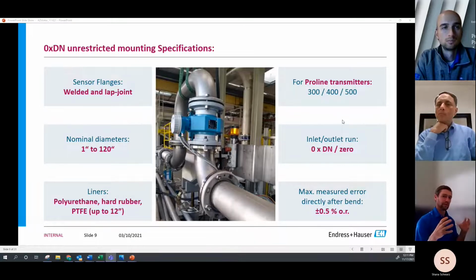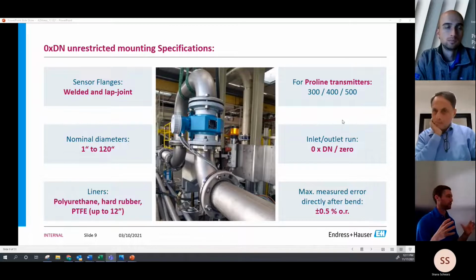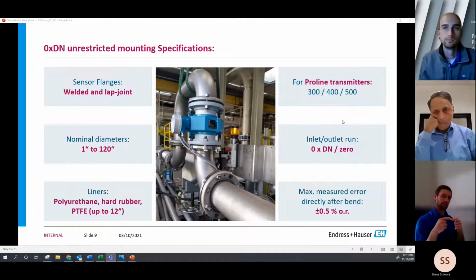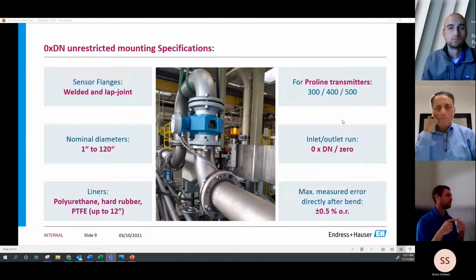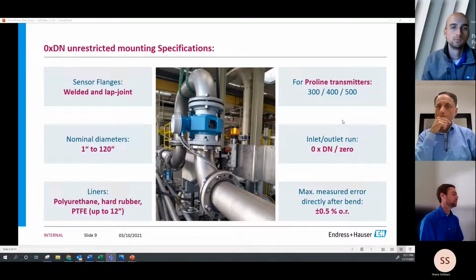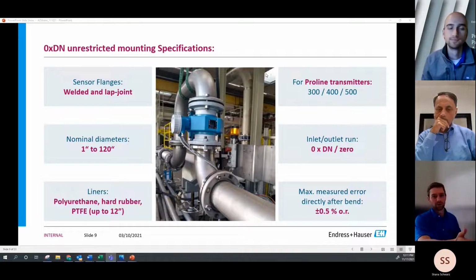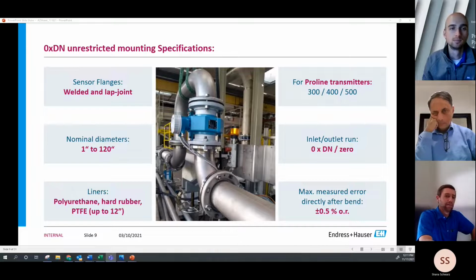If there's bolt holes that don't line up, what lap joint flanges are is they're just non-welded flanges along the sensor body itself, so they're able to rotate. So if you have bolt holes that are off by just a little bit, you can line those bolt holes up and get that meter to be mated to those flanges. Liners, just like our normal mag meter, we do have polyurethane. It's kind of the go-to in the water market. Hard rubber, go-to for wastewater applications, and PTFE for any of the chemically invasive applications.